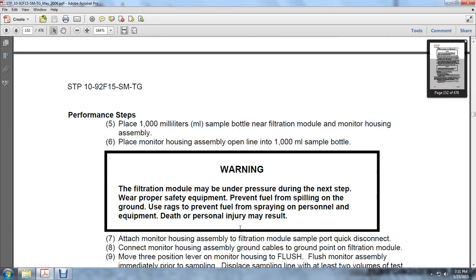The filtration module may be under pressure during the next step, so wear the proper safety equipment. Prevent the fuel from spilling on the ground. Use rags to prevent the fuel from spraying on personnel or equipment. Death or injury may result. Attach the monitoring housing assembly to the filter module sample port.